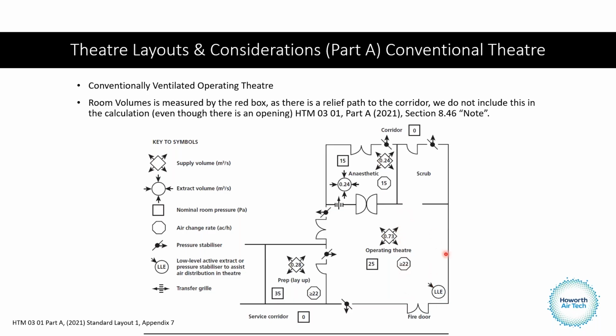So if we increase the size of this room to get to 22, we need to put more air in. So that's the perimeter of the room. That's important to know. Notice that the anaesthetic room at the top here has a balanced supply and extract. And remember what I said before: cross-flow ventilation, high-level supply, low-level extract, ideally angled as well. HTM gives us an idea that it should be angled, so that's important to note too.